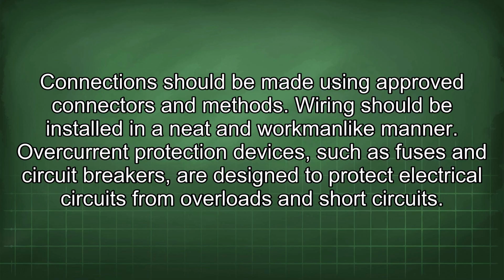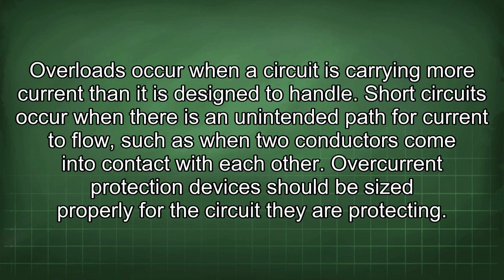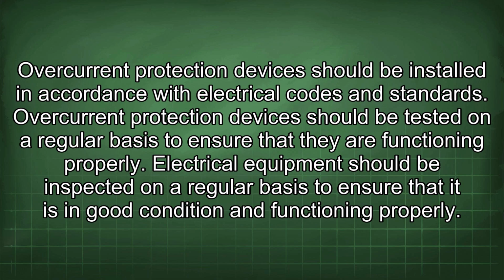Overcurrent protection devices, such as fuses and circuit breakers, are designed to protect electrical circuits from overloads and short circuits. Overloads occur when a circuit is carrying more current than it is designed to handle. Short circuits occur when there is an unintended path for current to flow, such as when two conductors come into contact with each other. Overcurrent protection devices should be sized properly for the circuit they are protecting. Overcurrent protection devices should be installed in accordance with electrical codes and standards. Overcurrent protection devices should be tested on a regular basis to ensure that they are functioning properly.